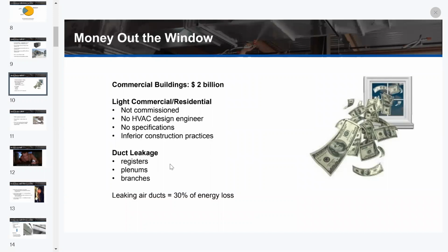It's a huge amount. Measurements reveal that light commercial buildings tend to have significantly higher duct leakage rates than large commercial buildings. Light commercial buildings typically are not commissioned, so duct leakage problems are not identified and fixed. In addition, smaller commercial building projects may not involve an HVAC design engineer and are more focused on minimizing first costs, which can lead to inferior construction practices.